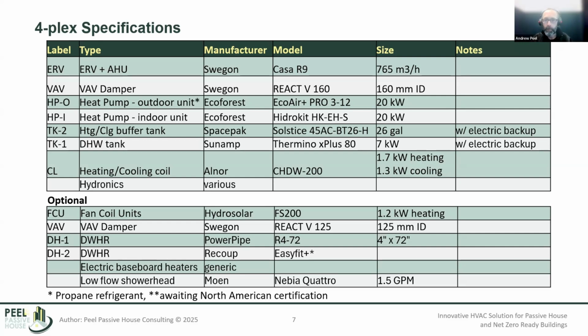The heat pump we've landed on is actually propane-based refrigerant, so that's something we navigate with local jurisdictions or building codes, though we haven't had issues so far. There's a benefit to propane in its extended range, colder water and hotter water, which is why it can handle all of the domestic hot water too.